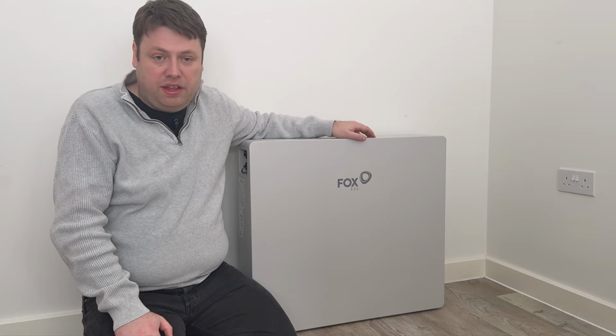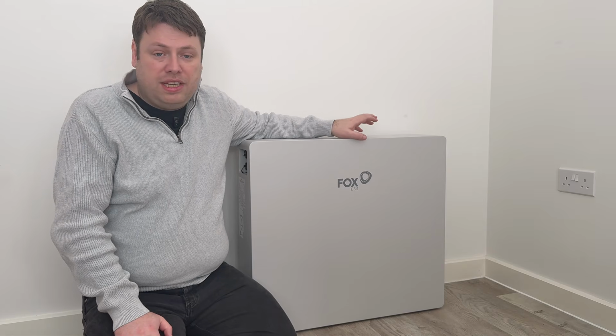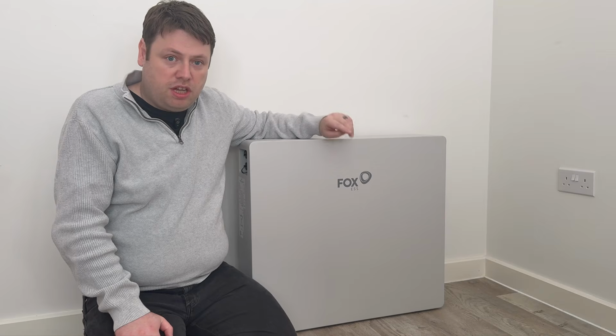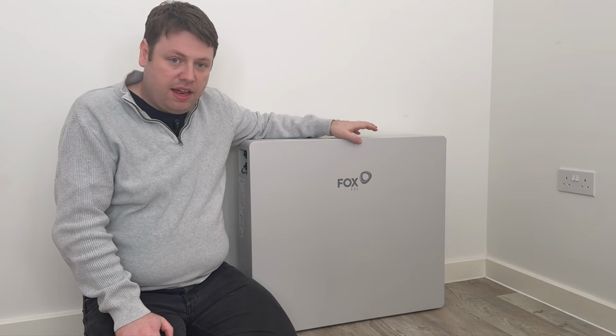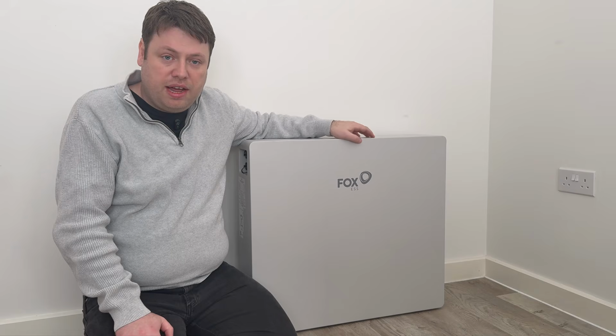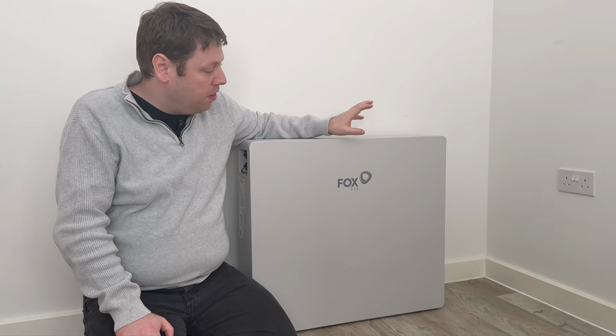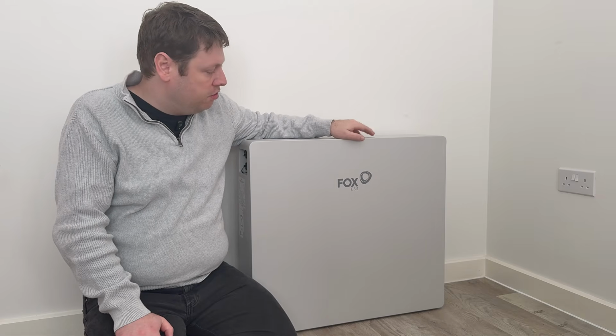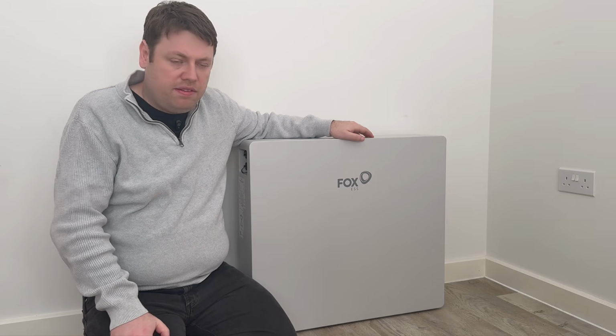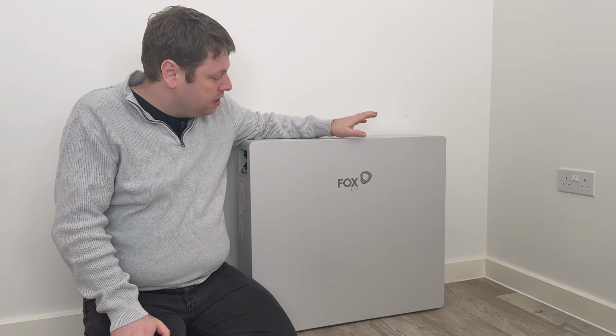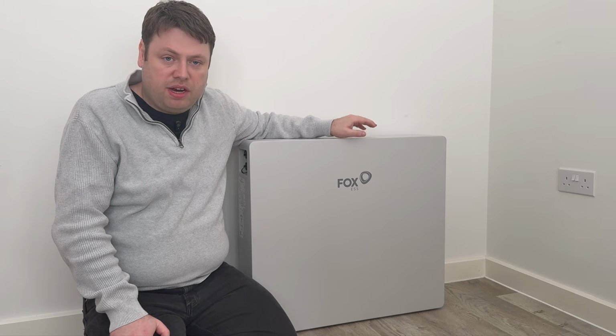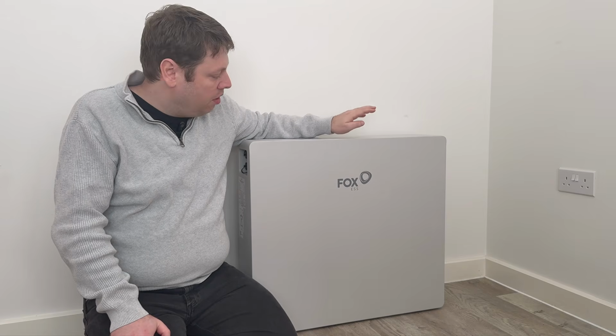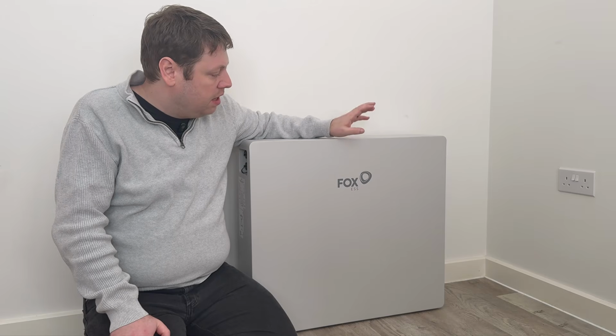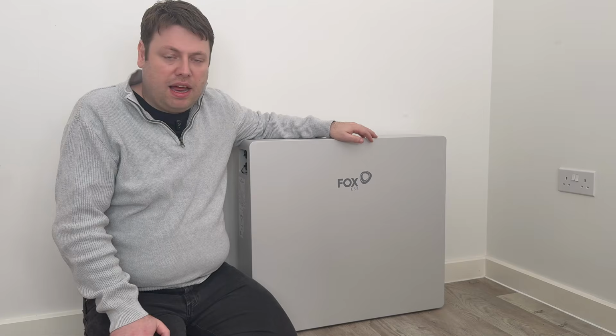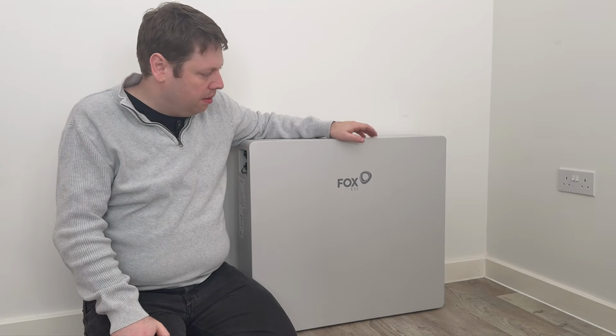Now if you add 4 of these together, it is over 46 kilowatt hours of storage, which at the time of recording, I believe is the largest storage you can have on a single inverter without going down the 3-phase route and having multiple CG6 battery setups on, say, a 3-phase H3 Pro. So if you're single phase using an H series inverter, a K series inverter, etc., you can go right from one module, 11.5 kilowatt hours, right up to 46 kilowatt hours, and actually it's 46.08 kilowatt hours exactly.